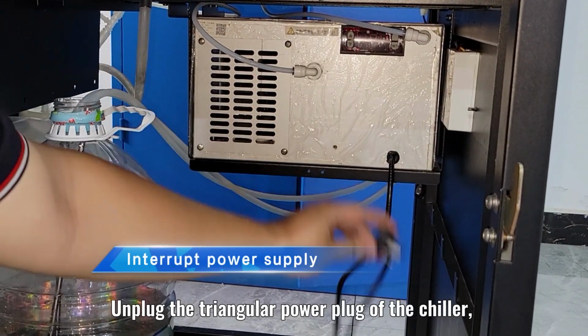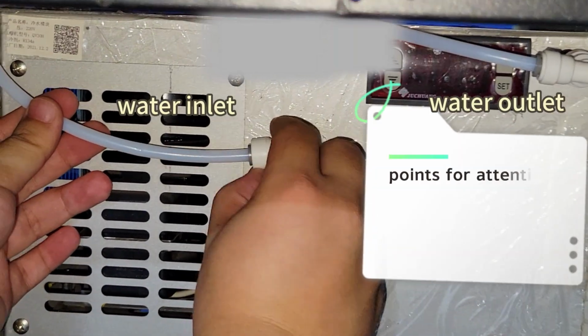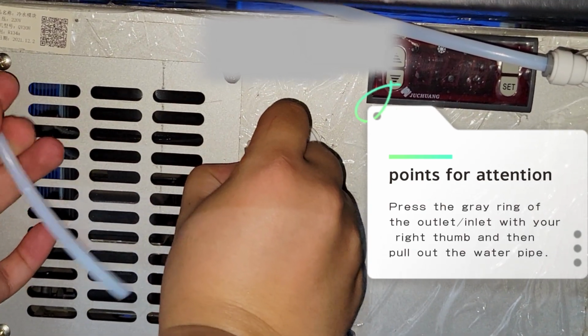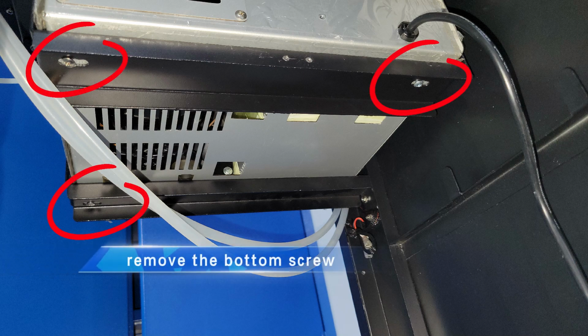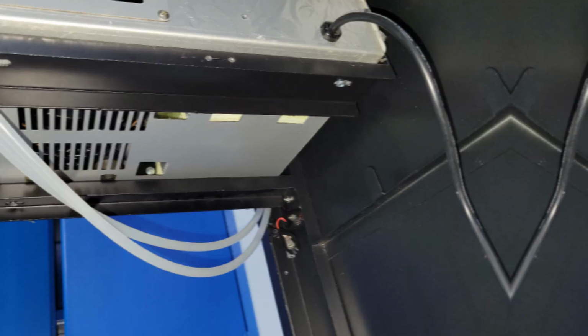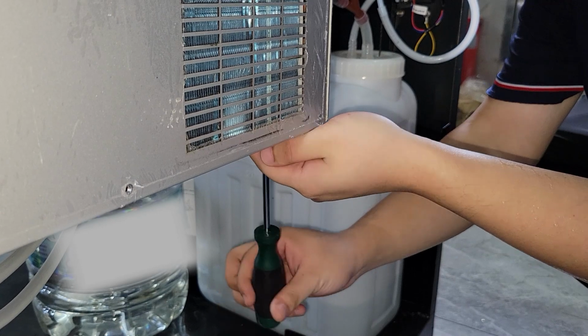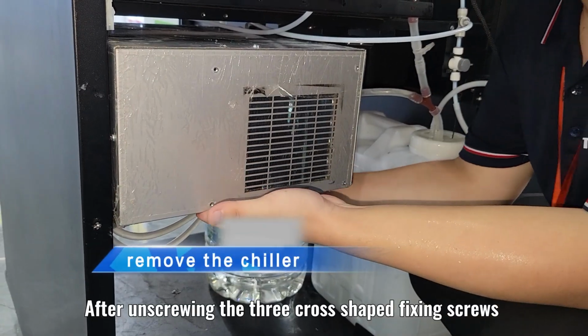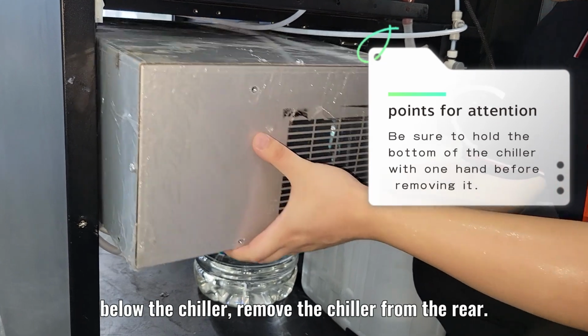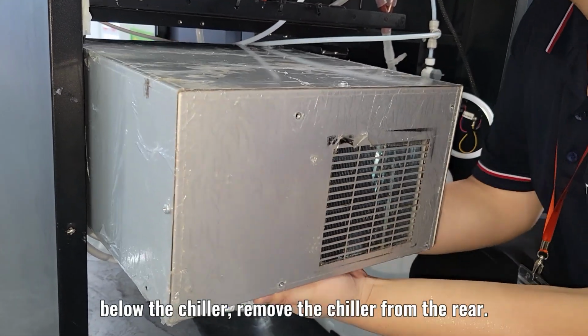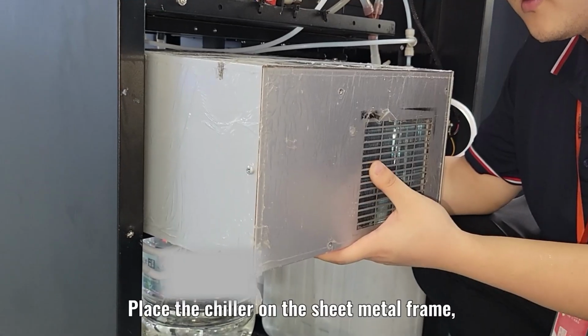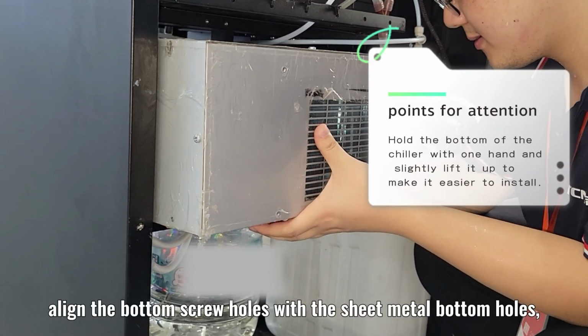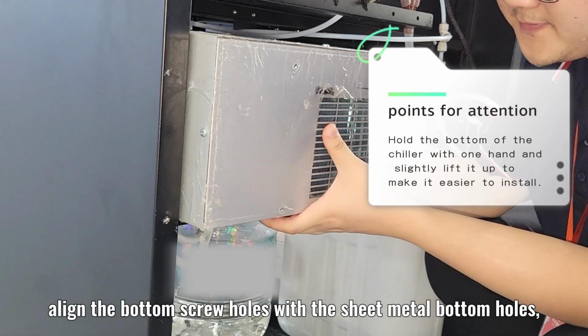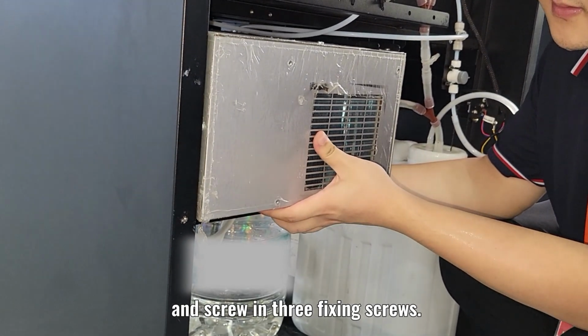Unplug the triangular power plug of the chiller, and then remove the inlet and outlet pipes of the chiller. After unscrewing the 3 cross-shaped fixing screws below the chiller, remove the chiller from the rear. Place the chiller on the sheet metal frame. Align the bottom screw holes with the sheet metal bottom holes, and screw in 3 fixing screws.